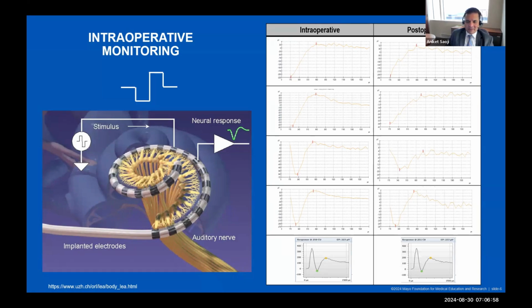One of the things that we did with the AB device as well as with the cochlear device was to measure streaming NRT. It takes about 2 seconds to get a good NRT response, because we present a biphasic pulse average, then present another biphasic pulse average, and we keep doing this for 2 seconds. And here comes a nice, beautiful N1P1 response. If we keep running this in a loop, you push the button once and it is measuring the response. This is the most commonly measured response during vestibular schwannoma resection, especially the electrically evoked compound action potential to monitor the auditory nerve.